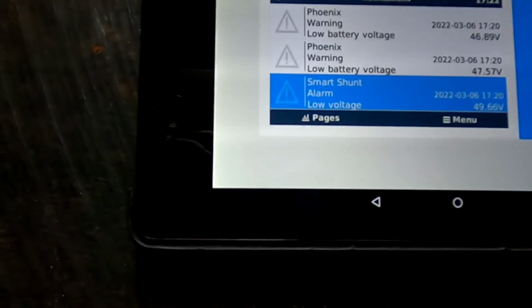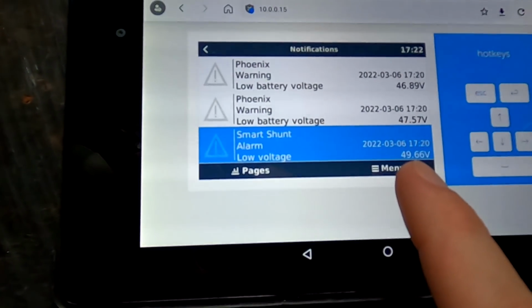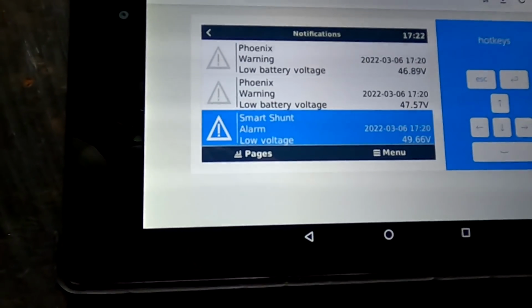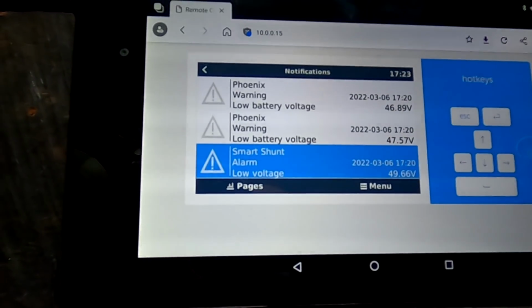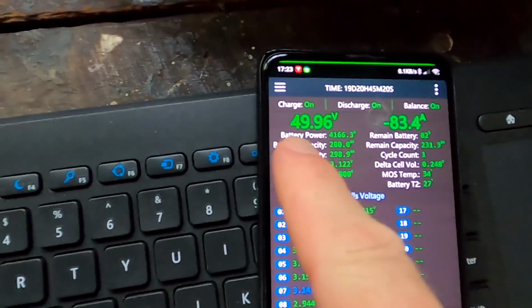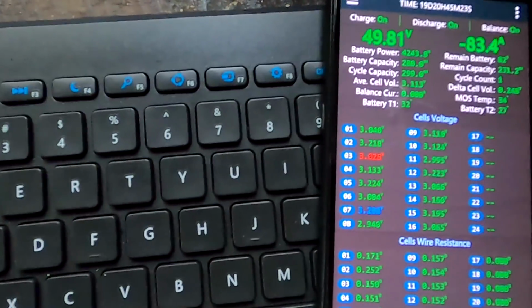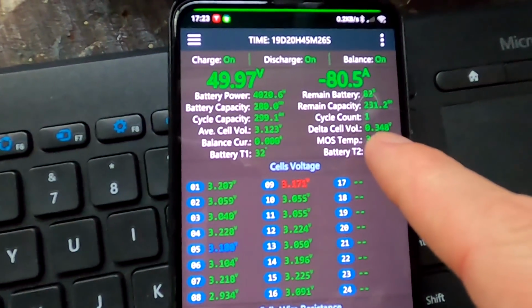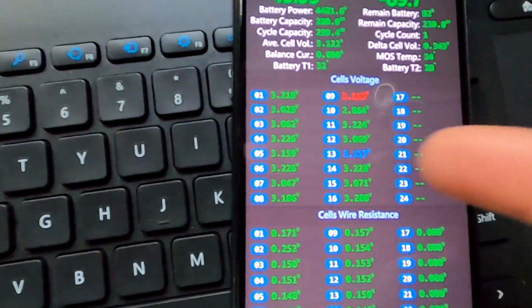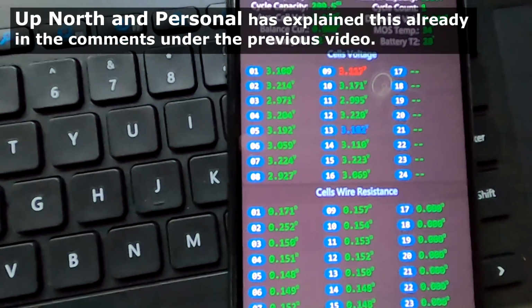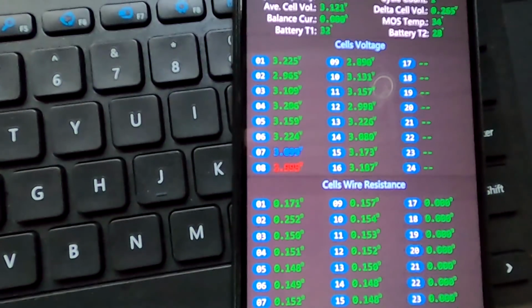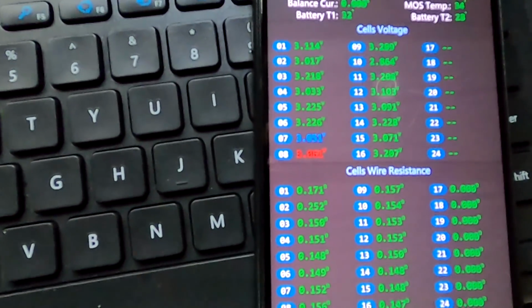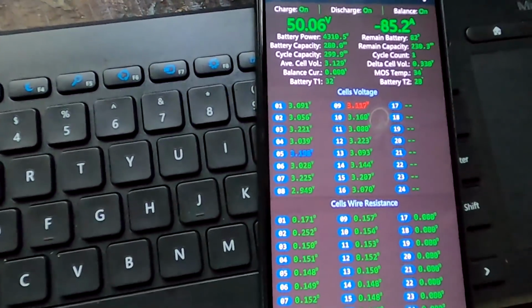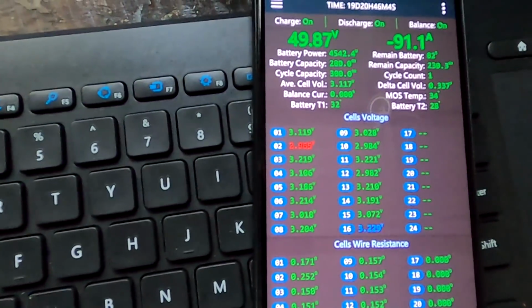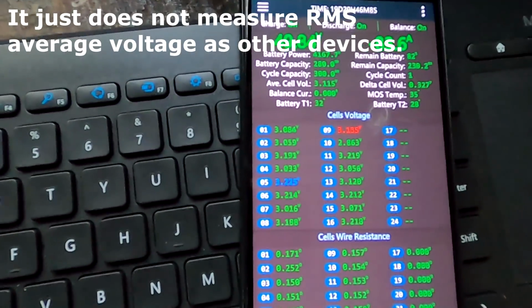Well, Houston, we've got the first problem here. The smart shunt actually claims we have a low voltage warning, under 50 volts. That cannot be true, minus 85 amps and just under 50 volts we have. And we have a delta of 350 millivolts across all cells. What the heck is going on here? We had this before when we tested the JK-BMS, and the voltage readings are jumping all over the place now. Some go even down to 2.9 volts. But when you actually measure the voltage of each individual cell, they are perfectly constant. So I'm not sure what's going on with this JK-BMS here.